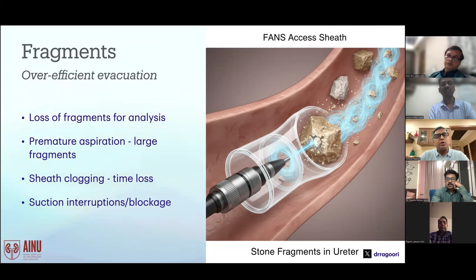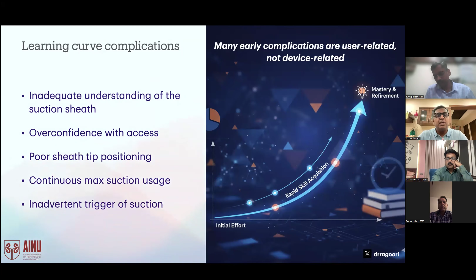Using an access sheath does take its own sweet time to get the hang of. An inadequate understanding of these suction access sheaths can result in any of the challenges we discussed, and overconfidence in using this access can also result in some issues. Poor sheath tip positioning, like I keep telling you, you need to get a hang of this before you start getting confident.